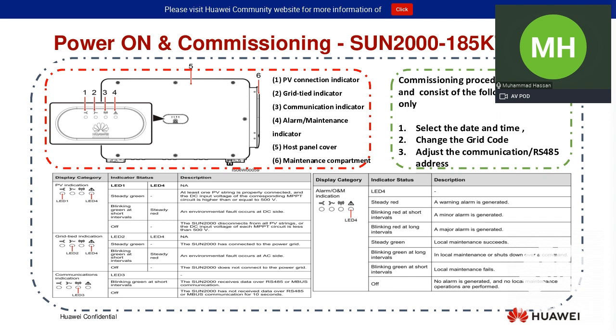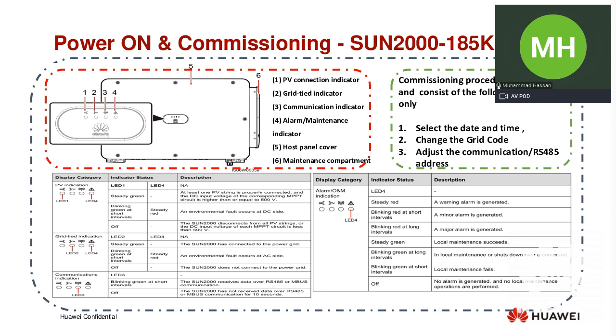The commissioning procedure is very simple. For all of our inverters, the commissioning procedure is the same. There are only 3 steps involved in the commissioning of the inverter. There is no cold commissioning and then hot commissioning procedure for our inverters. We just follow the 3 steps. You connect the SUN2000 app to that inverter, or if you are using smart loggers for utility scale, you can do the commissioning from both equipments.